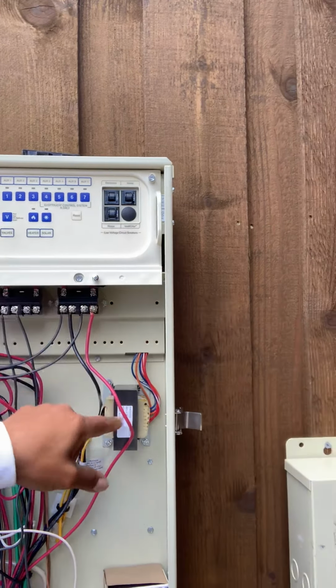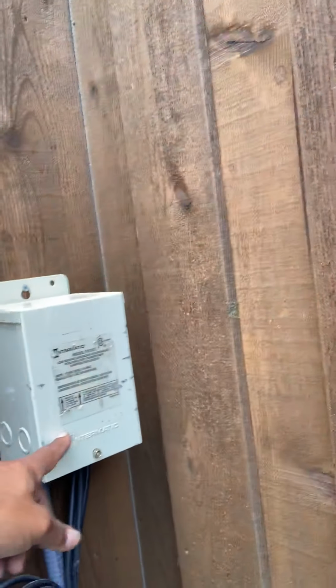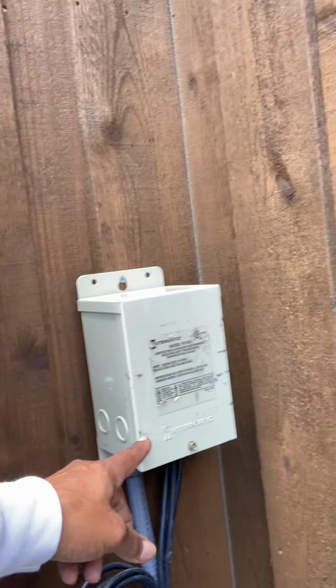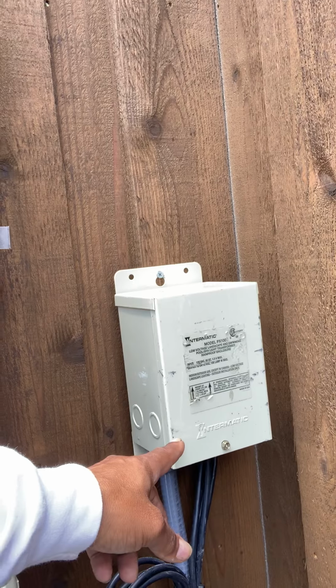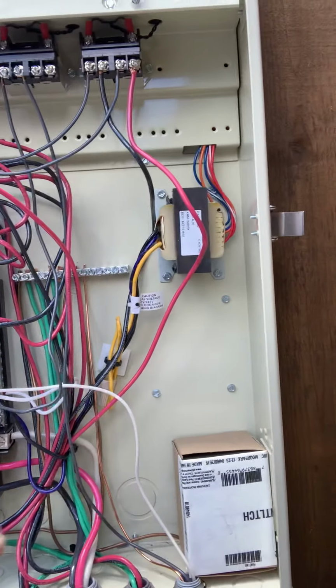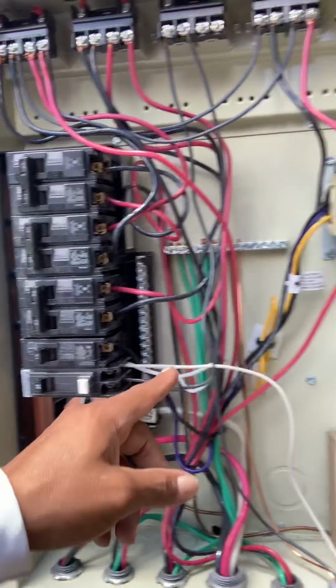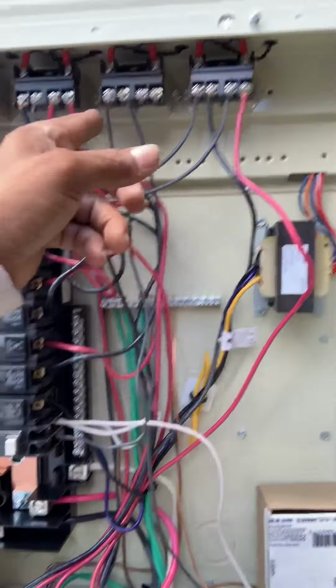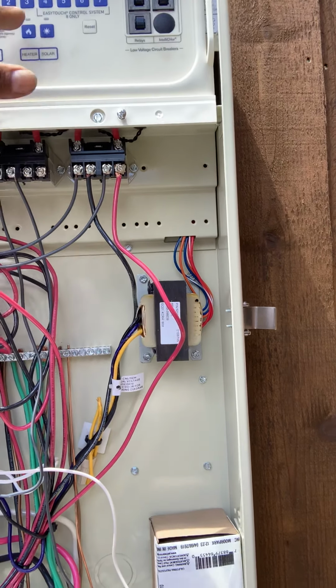And then the GFCI for the lighting transformer, for the low voltage lighting for the swimming pool, the transformer goes from the GFCI breaker to the lighting contactor, from the lighting contactor straight down to the lighting transformer. So it is on an auxiliary, which is auxiliary 2 or 3, I think it's 3, for the lights.